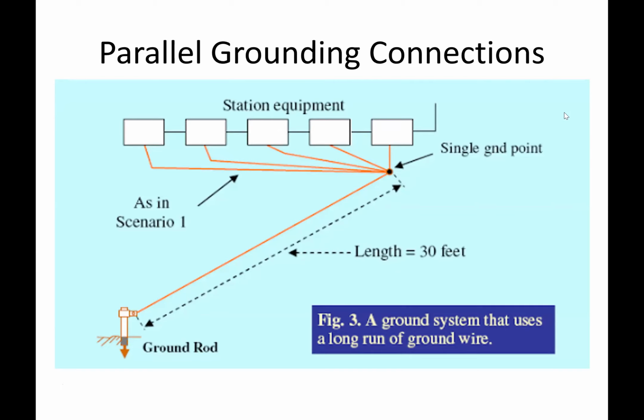To make sure that the station is grounded before anything enters the building. So the grounding rods outside, all these single point grounds, are connected to a copper plate which is outside. Everything is grounded to one point.